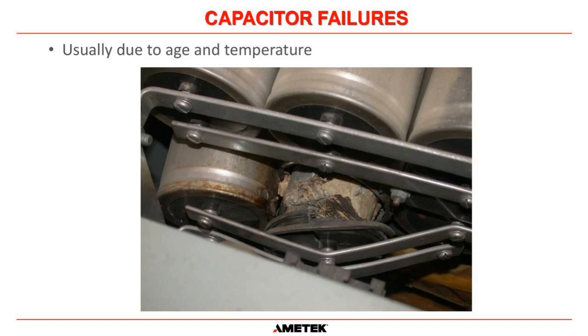So the next mode of failure is capacitor failures. Now, you can see in that picture there, this is what the bus bars should look like. They should be absolutely straight and even. This bus bar here should be going over here, and you can see that this capacitor here, surprisingly enough, should not look like that. That has been a sudden failure of that capacitor, and capacitors usually fail due to age and temperature. Okay, and especially DC electrolytic capacitors, which is what this capacitor is.